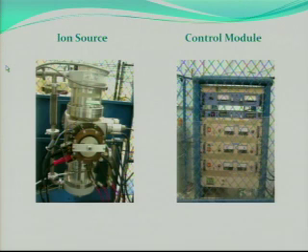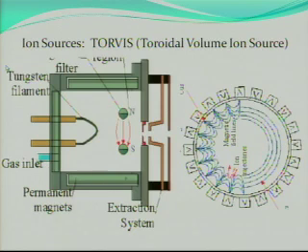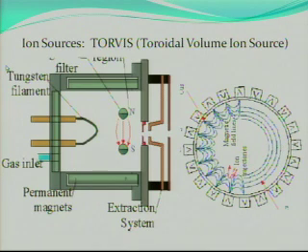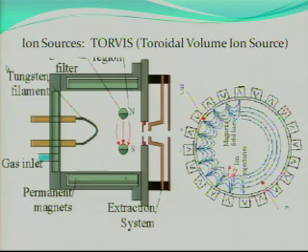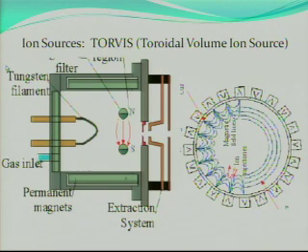These two pictures are the ion source and the control module. For proton irradiation, we use a negative hydrogen ion. The hydrogen molecule enters the chamber and collides with high-energy electrons. The aperture on the right side will extract the negative hydrogen ion.